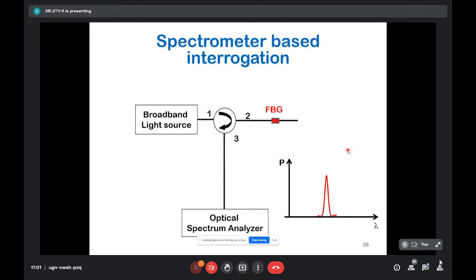So one of the simplest techniques is the spectrometer-based interrogation, where you use a broadband light source to illuminate the FBG sensor, and then you use an optical spectrum analyzer to capture the spectrum. Okay, and you see a device here. This is called a circulator, a 3-port circulator, where it allows propagation only in one direction, the clockwise direction. So whatever you input into port 1 gets transmitted to port 2, so that goes to your FBG. And from the FBG, you know that there is a reflection that's coming. So the reflection comes to port 2, it goes to port 3, and it is captured by your optical spectrum analyzer.